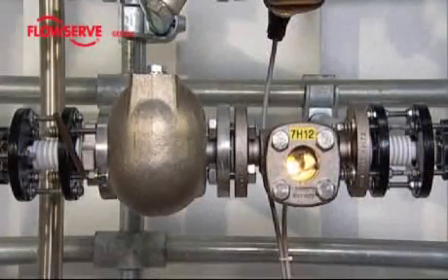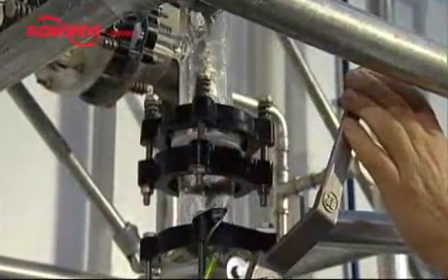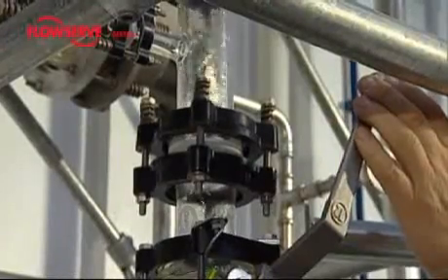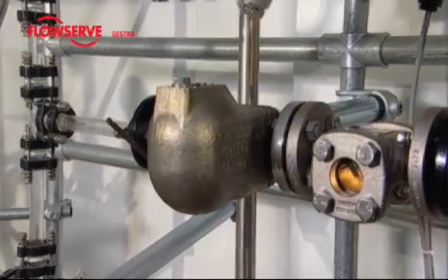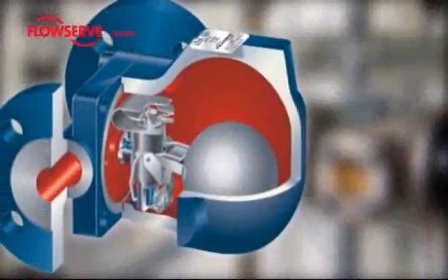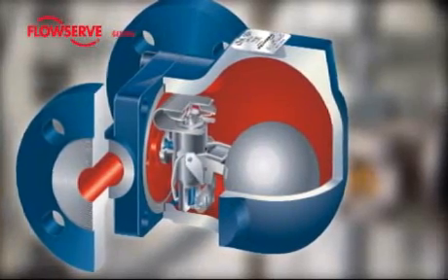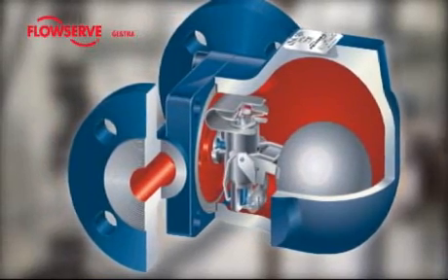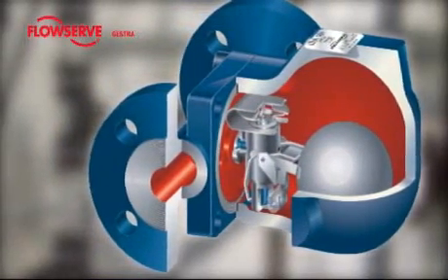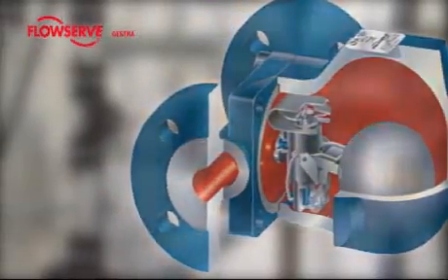If the steam is controlled and the steam pressure varies as a result, this will have hardly any influence on the condensate discharge, which will still be controlled solely by the level in the trap, independently of pressure and temperature. Owing to the large volume offered by the body of a ball float trap, fluctuations in flow rate can be handled easily — the steam trap is not prone to hiccups. Because the flow velocities are low, particles of dirt can precipitate at the bottom of the body and will therefore not influence the seat tightness at the orifice.